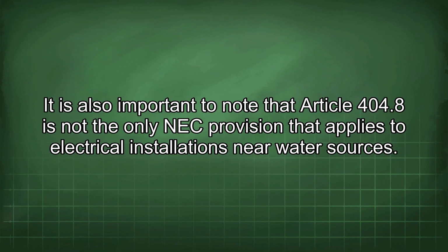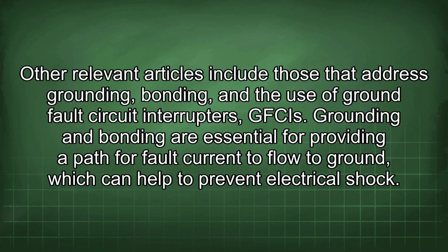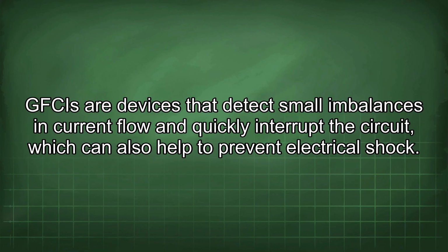It is also important to note that Article 404.8 is not the only NEC provision that applies to electrical installations near water sources. Other relevant articles include those that address grounding, bonding, and the use of ground fault circuit interrupters, GFCIs. Grounding and bonding are essential for providing a path for fault current to flow to ground, which can help to prevent electrical shock. GFCIs are devices that detect small imbalances in current flow and quickly interrupt the circuit, which can also help to prevent electrical shock.